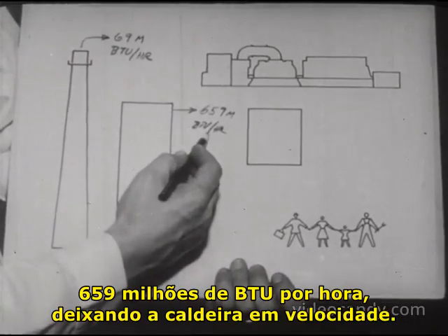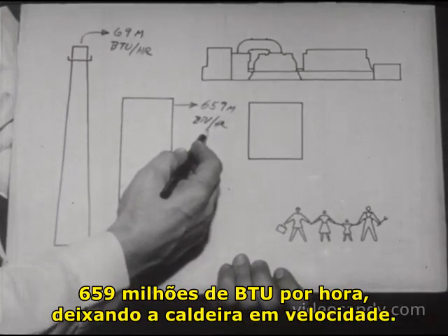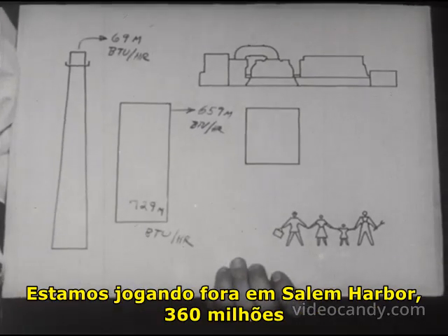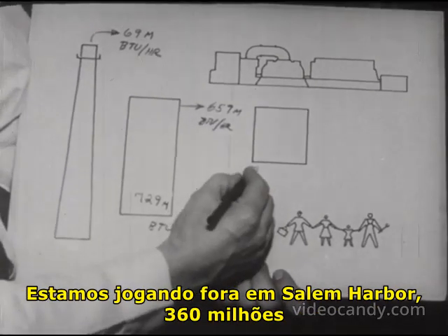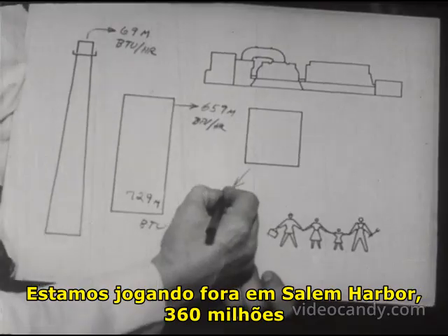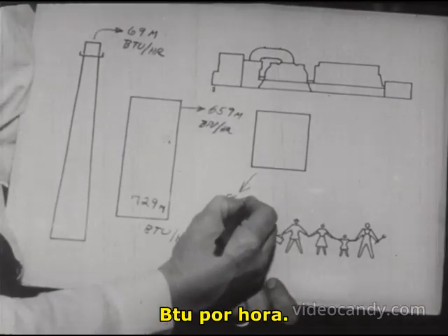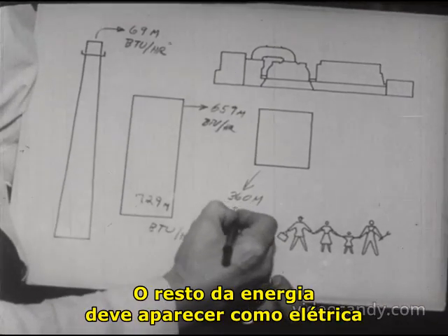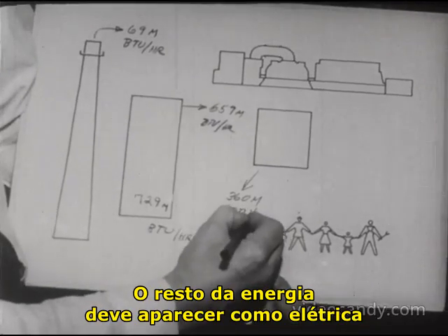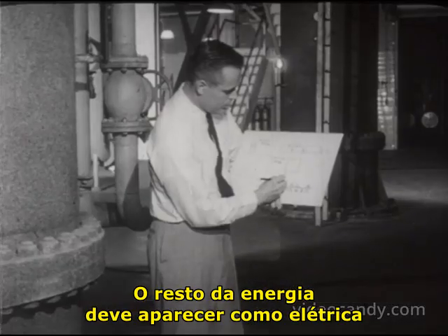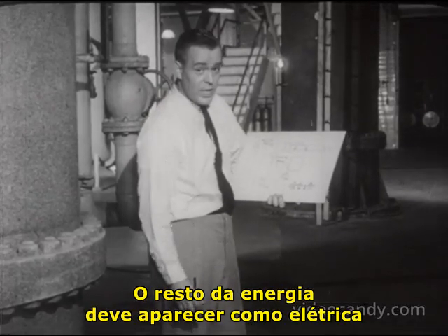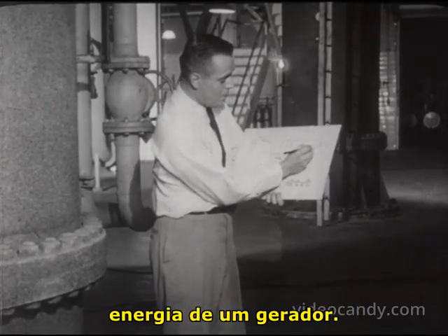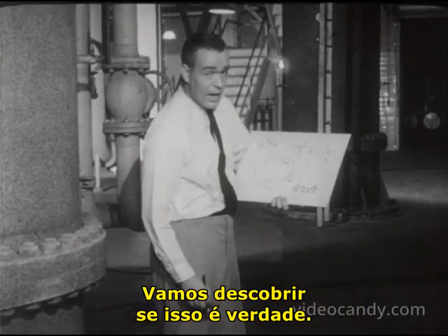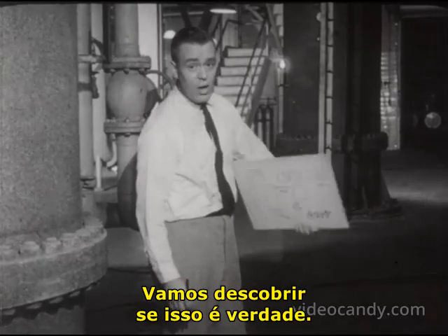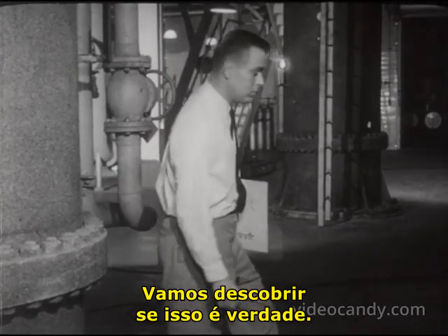We had 659 million BTU per hour leaving the boiler as steam. We're throwing away to Salem Harbor 360 million BTU per hour. The rest of the energy should show up as electrical energy out of the generator. Let's go and find out if this is true.